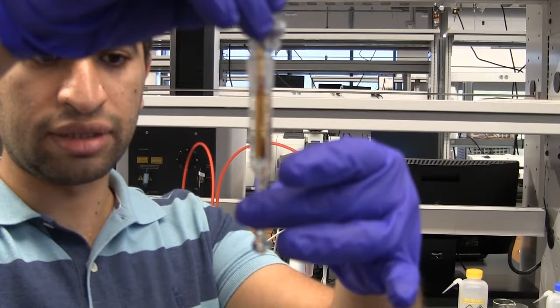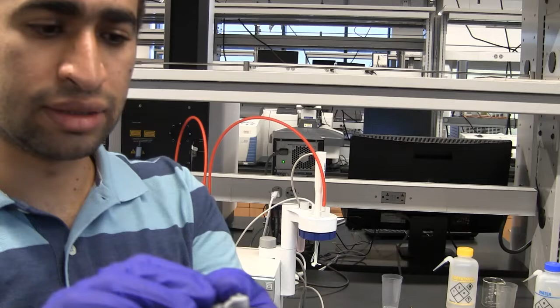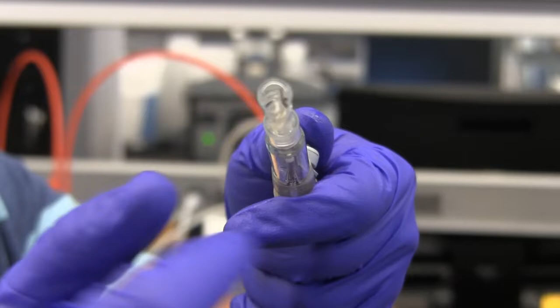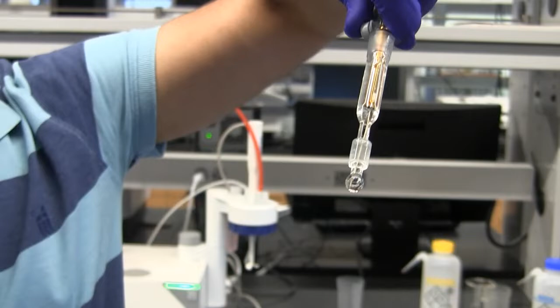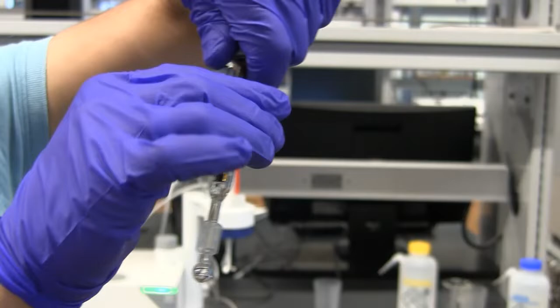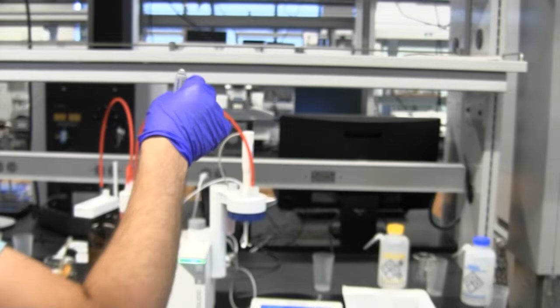So one more thing, you can also check that this glass slider can rotate. If it's rotating, that means it's working fine. If it's not, then you close the cap and put it upside down and then move it and then wash this area with distilled water and then put it back. Do this and then shake it a few times to make sure there are no air bubbles inside. And then open the cap again for your experiment. Okay? And put it back in here.